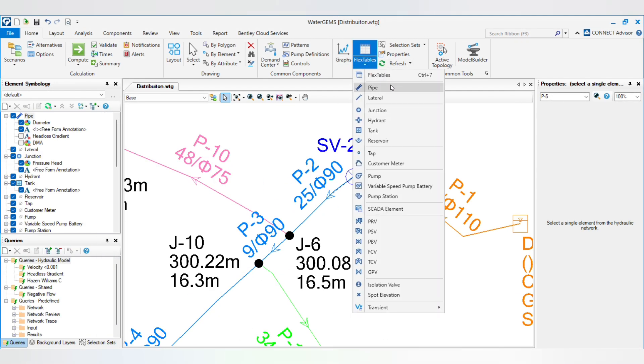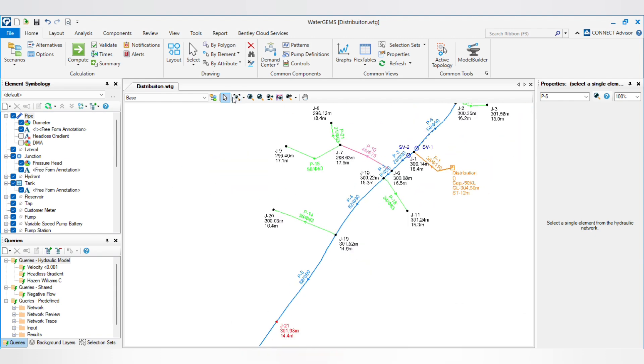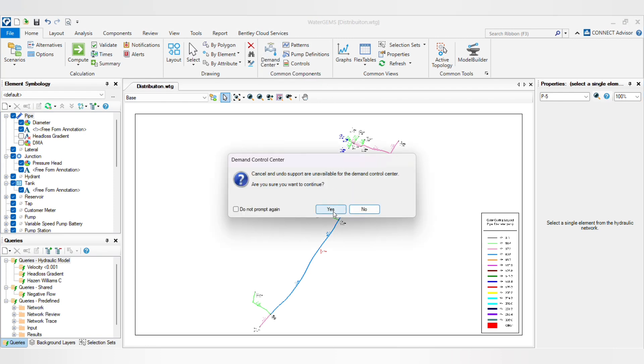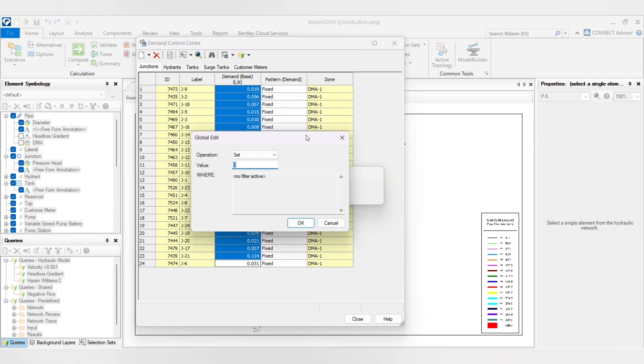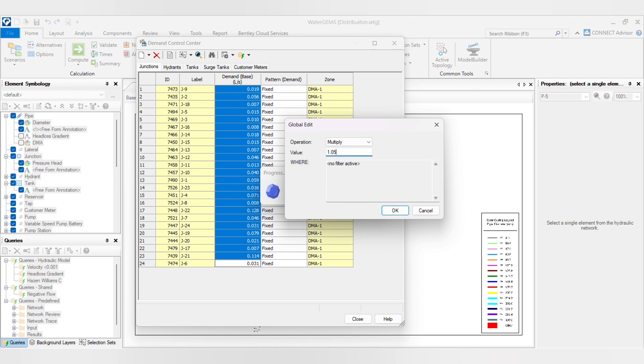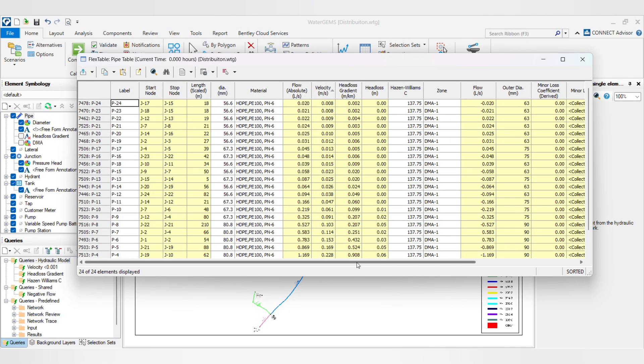The second method is to increase the total demand by 5%. You can either increase it manually before putting demand into the network, or go to the demand control center. Click yes when prompted — be careful, because changes in the demand center cannot be undone. Multiply the demand by 1.05 to add 5% losses.